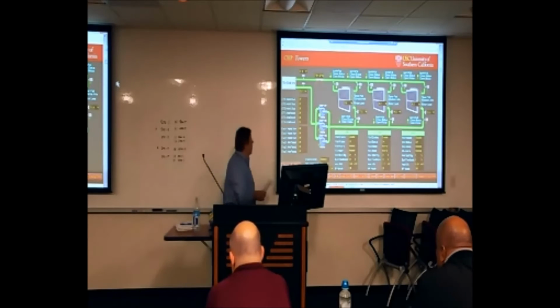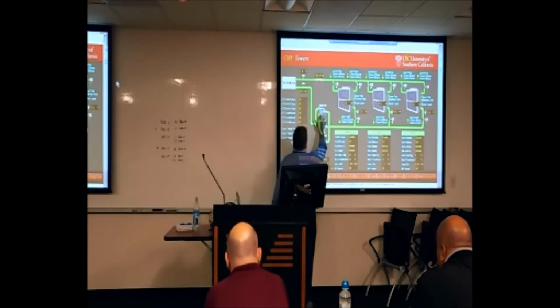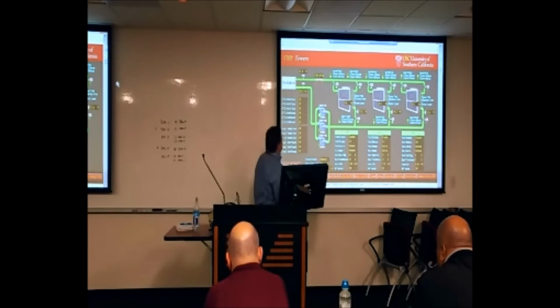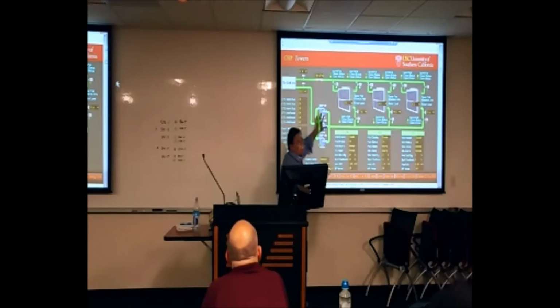Okay, so that was how to observe the pump data, by clicking on the pump. It'll pull up that little pull-up, and you can see the data for the pump. Each one of these pumps can fail by 2 means. One is a VSD failure will immediately fail the pump, or 2, if we have a status mismatch. If we've command on a pump and haven't seen the status come back after 30 seconds, then we're going to fail the pump. So if a pump fails, it just gets shut down. The next pump in the lead lag rotation is going to start and operate, and so on into the next pump. And there we'll need alarm reset. In other words, when we fail, the pump gets locked out.